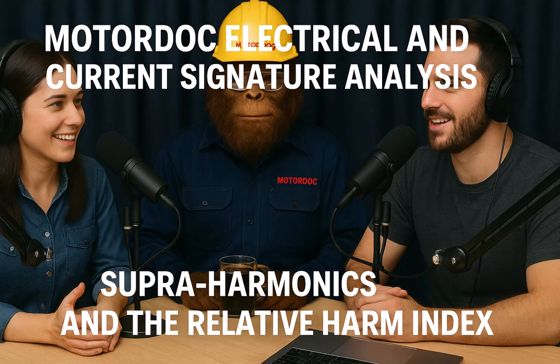What if the insulation completely breaks down? Insulation to ground fault. How does that show up? Interestingly, a major ground fault can actually show up in the analysis of the ground conductor itself. On the ground wire. Yeah. In bad cases, the frequency spectrum you see on the ground can almost mirror the mainline frequency spectrum. And usually you'll see higher leakage current flowing to ground too.